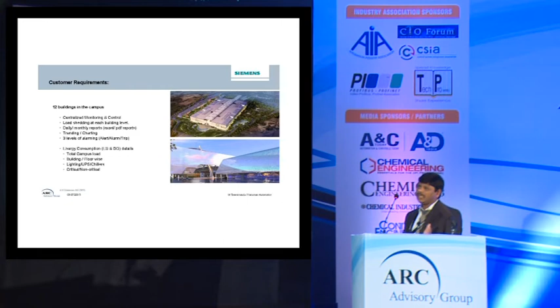So that's what they wanted at each building level - one building may have 10 MVA, another 5 MVA, another 4 MVA. And energy consumption they wanted building-wise and floor-wise, and even beyond floor-wise: lighting, how much energy it's consuming, UPS, chillers, floor lighting, external lighting, and what are the critical loads versus non-critical loads they are consuming. That's what they wanted to have.